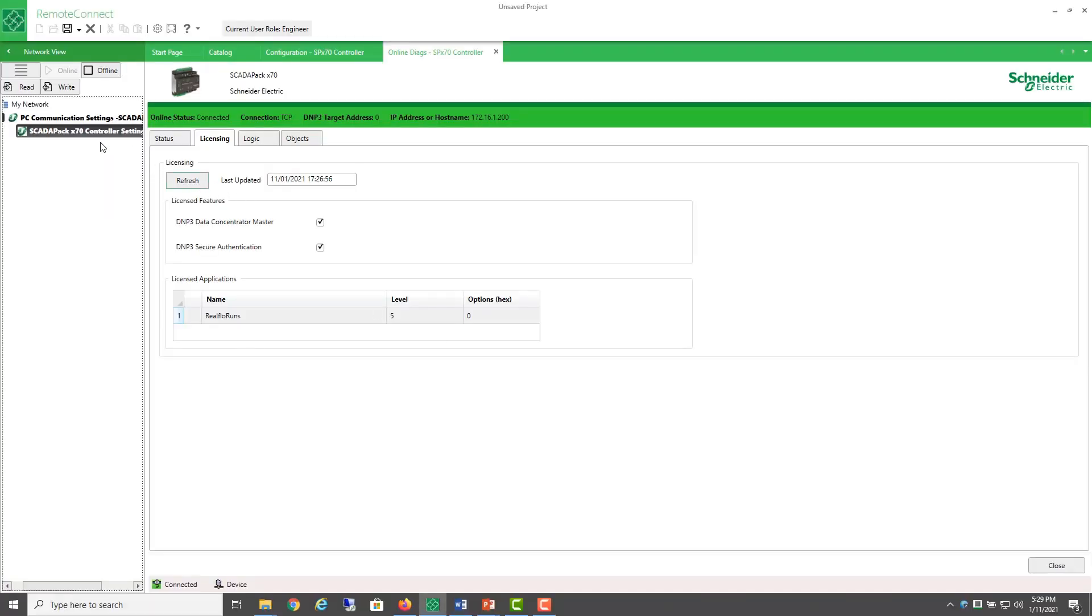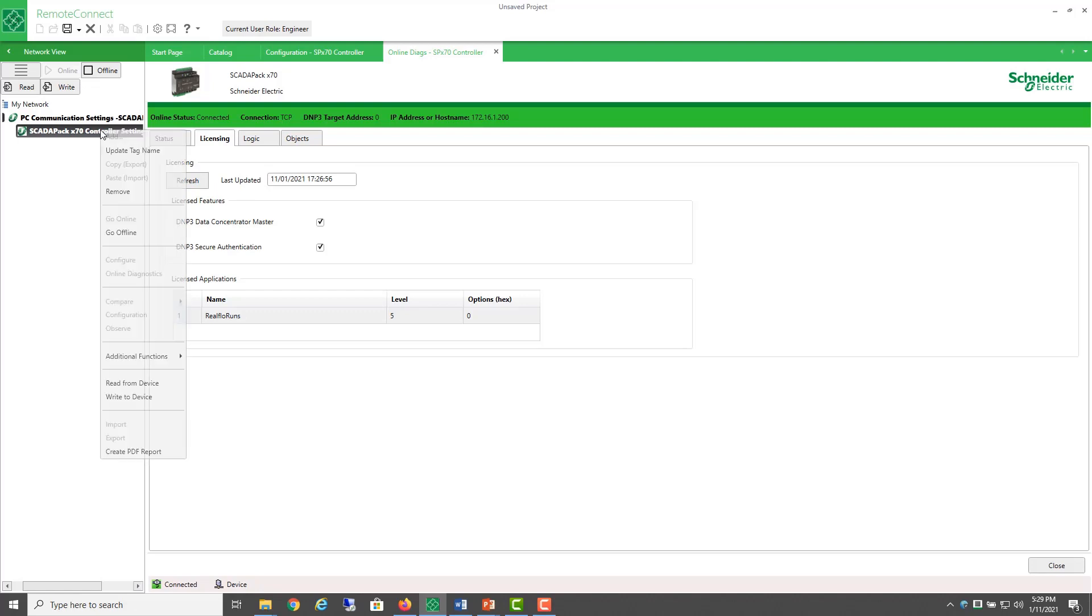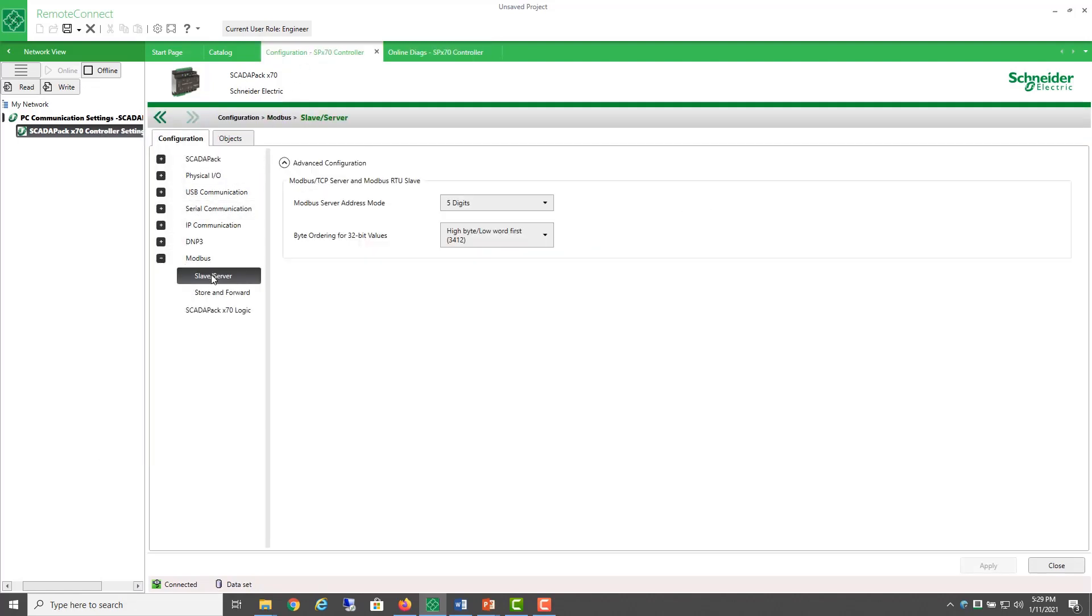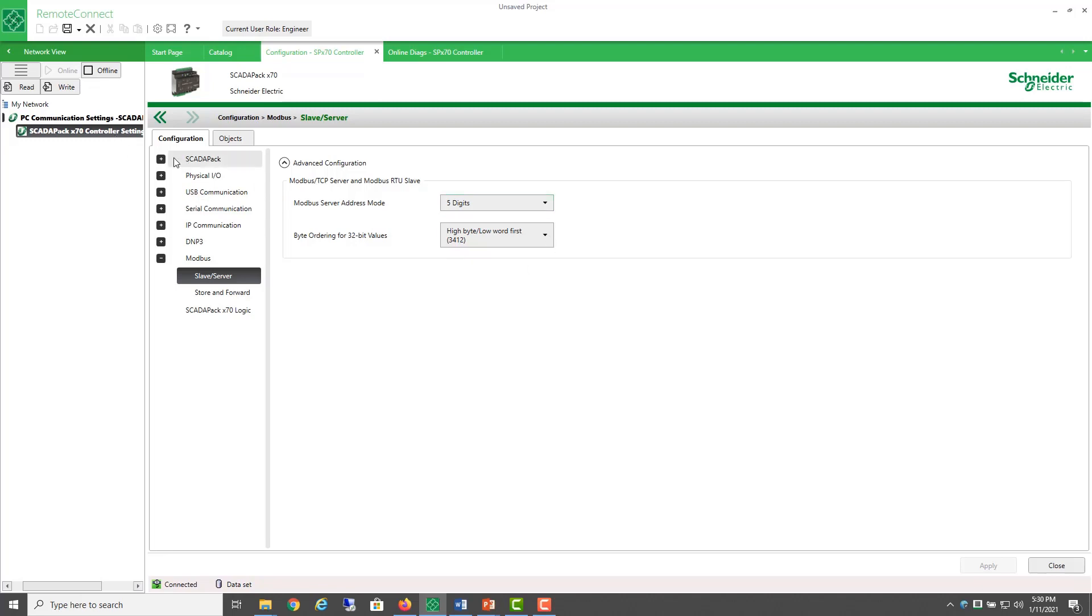Now, the settings for Modbus RTU begin with a default byte order for 32-bit values of the high byte first and the low word. So, we've got 3412 is the byte order. Now, watch what happens when we enable the flow computer on this existing project with a default byte order.